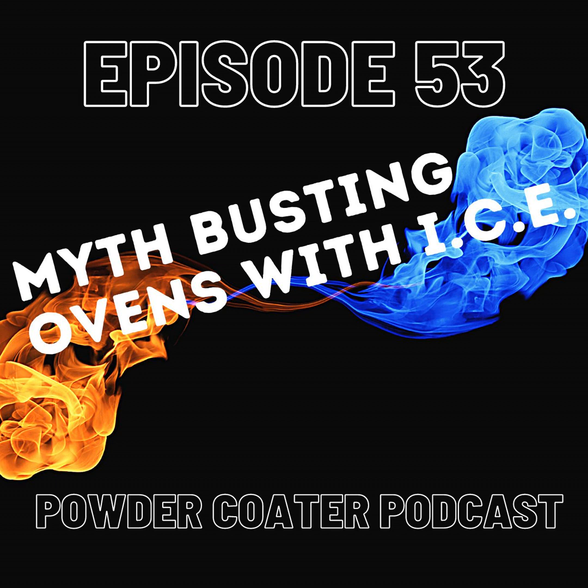Yeah, the standard oven wall insulated panel is typically a 20 gauge, either aluminized or galvanized. Aluminized is a little bit better material. A lot of ovens are built out of galvanized, and that's fine. The only issue with galvanized, especially if you use it in a heater house, is that when you hit about 800 degrees, it crystallizes. You can hit it with a hammer and it will shatter as if it was a piece of glass. I've physically seen that happen. But typically aluminized 20 gauge in and outer skin, or 2.5 millimeters depending on what steel you're using, is more than sufficient. The big issue is insulation.